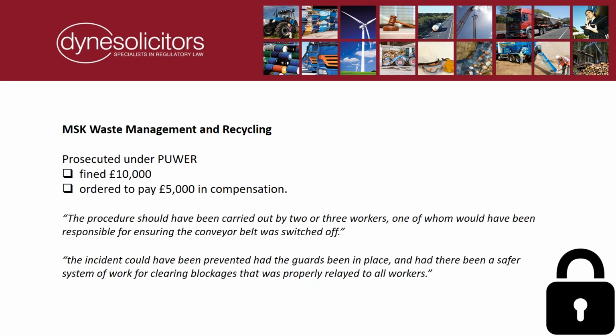Another case that has been sentenced very recently, again, is not on the slide, is Viridor, a very well-known waste recycling organisation. Viridor was fined £650,000. In that case, an employee entered a ballistic separator to clean it. The ballistic separator had been switched off, but while the employee was doing whatever he was doing, and I don't think Viridor fully understand what he was doing there in the first place, but whilst he was there, the power was turned back on in the control room, and the rest you can guess.